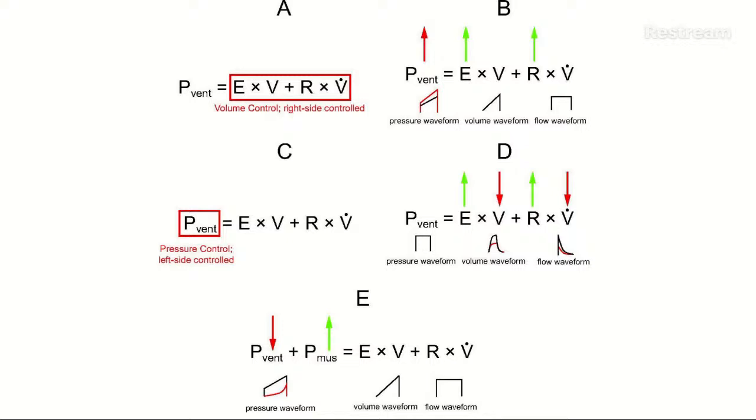So I'm giving volume, what I have said, but patients might have worsened, because now for achieving that volume, it calculates the resistance and elastance and then increases the pressure to get the desired target of volume that you have set.